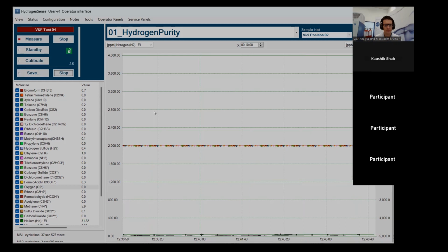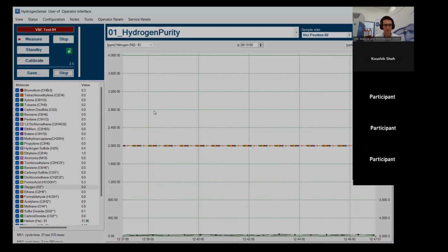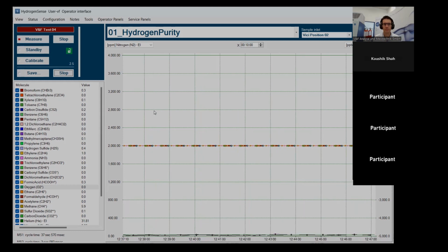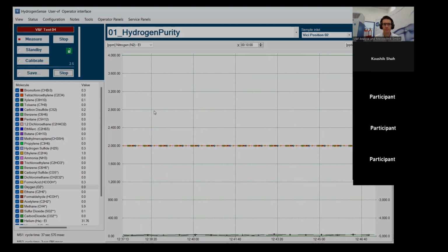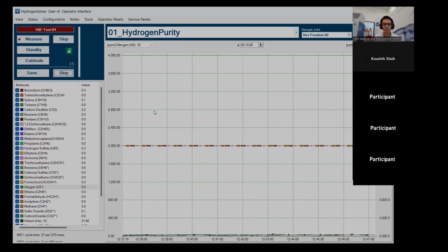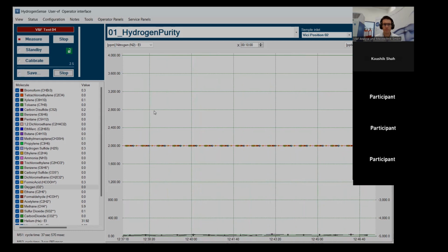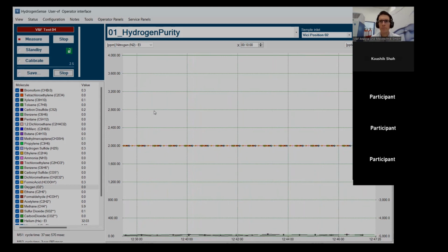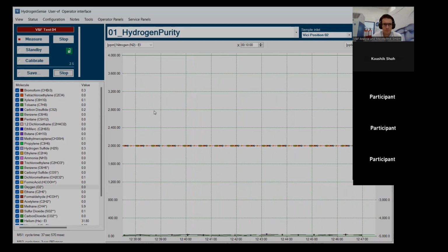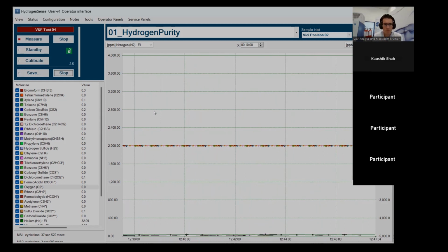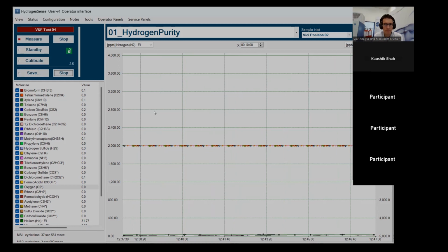Twice a week. Okay. Coming back to the core question about the calibration standards, you said it is not in your scope of supply. No, not in our scope of supply. So my next question is, there will be ambiguity in the standard quality, typically for ammonia, formaldehyde, acetaldehyde, even sulfur species or halogens. Different halogens have different boiling points. How to make sure that it is in the same phase? So in this situation, how are you ensuring that users are able to calibrate your instrument appropriately and get the right result, because getting the right standard itself is a challenge?